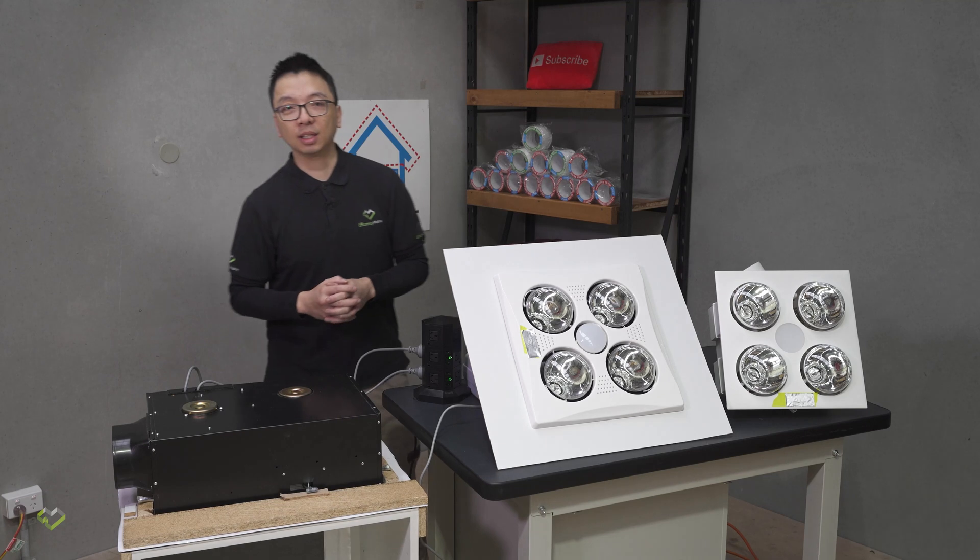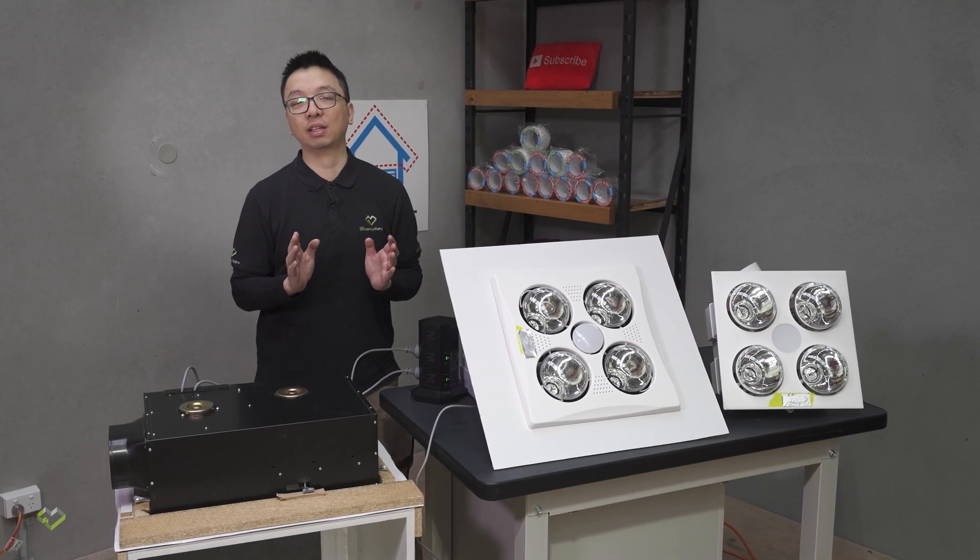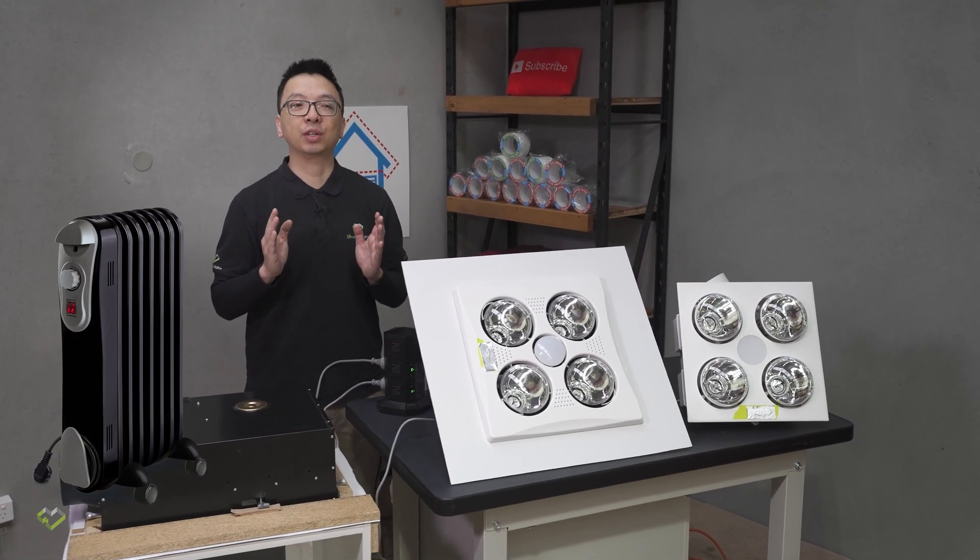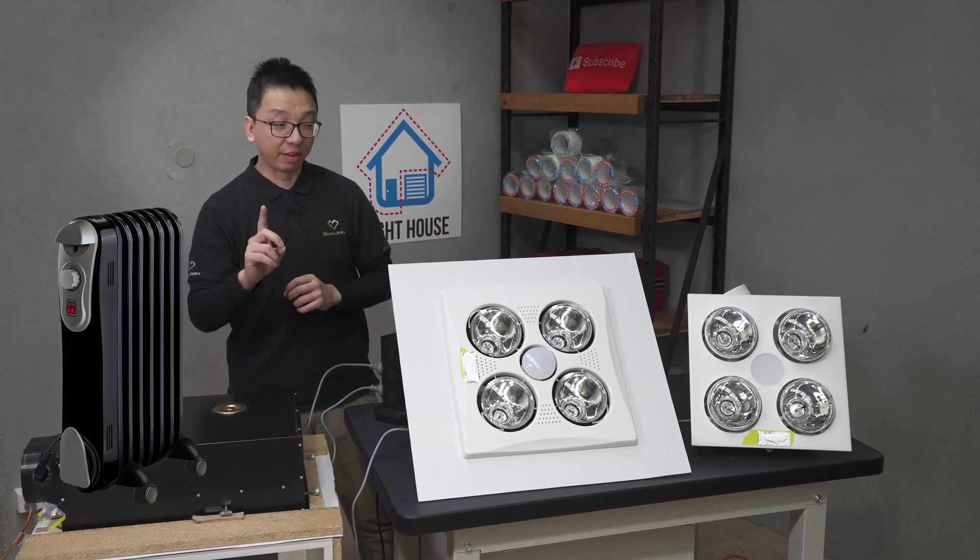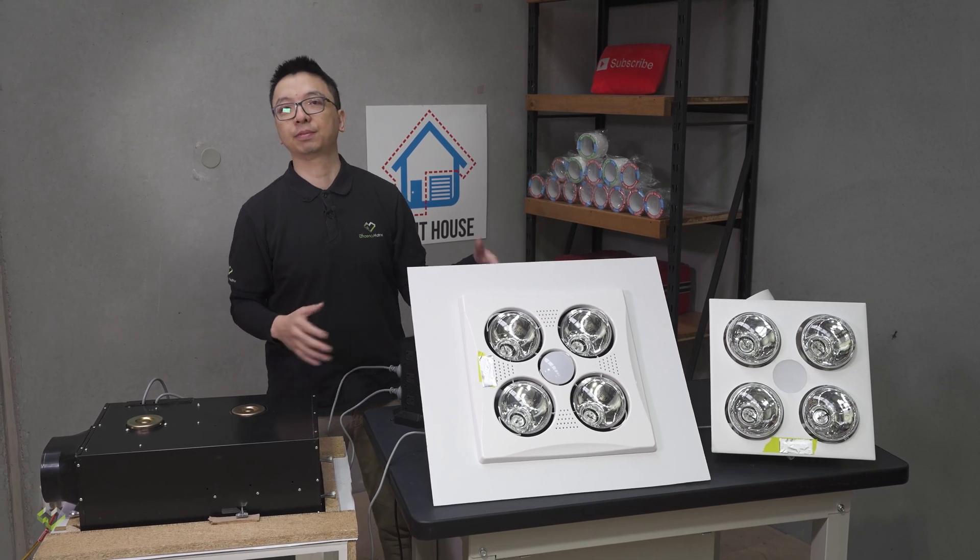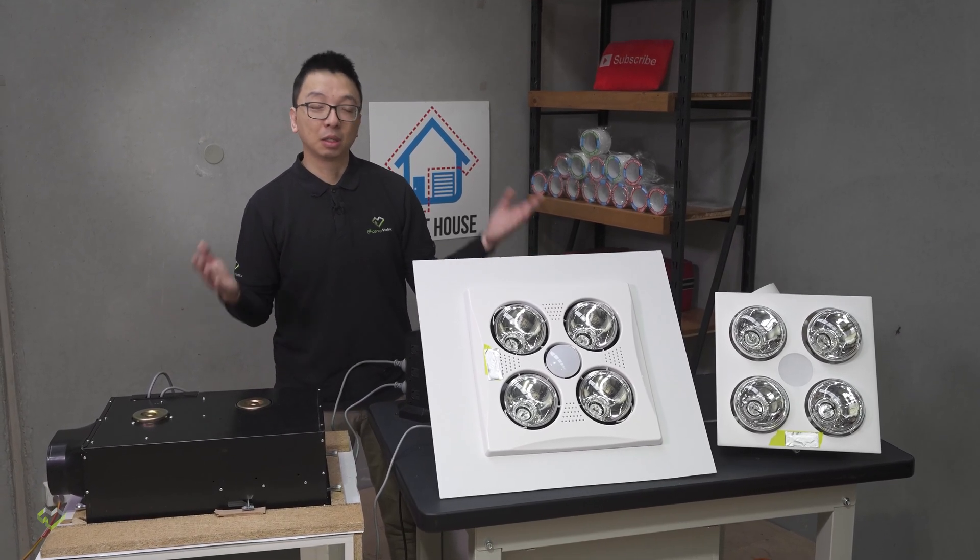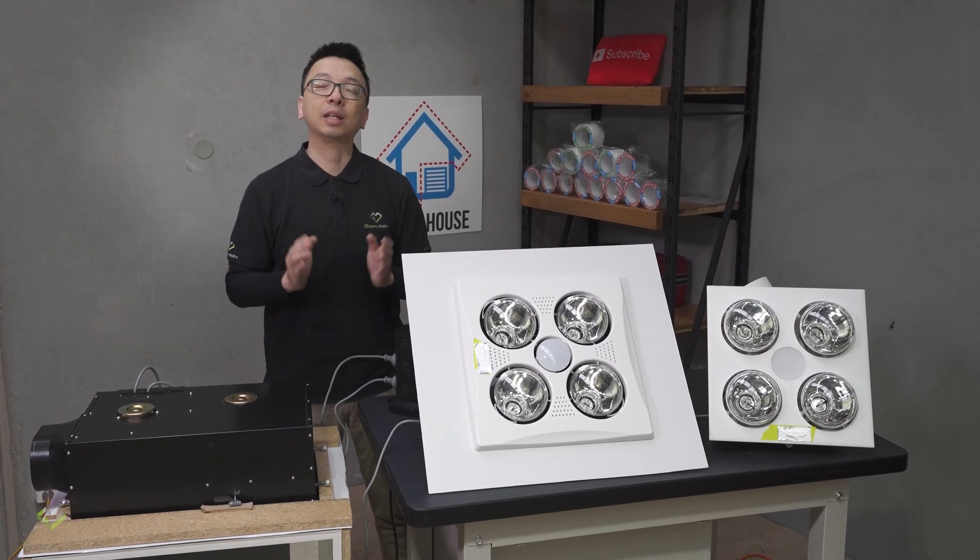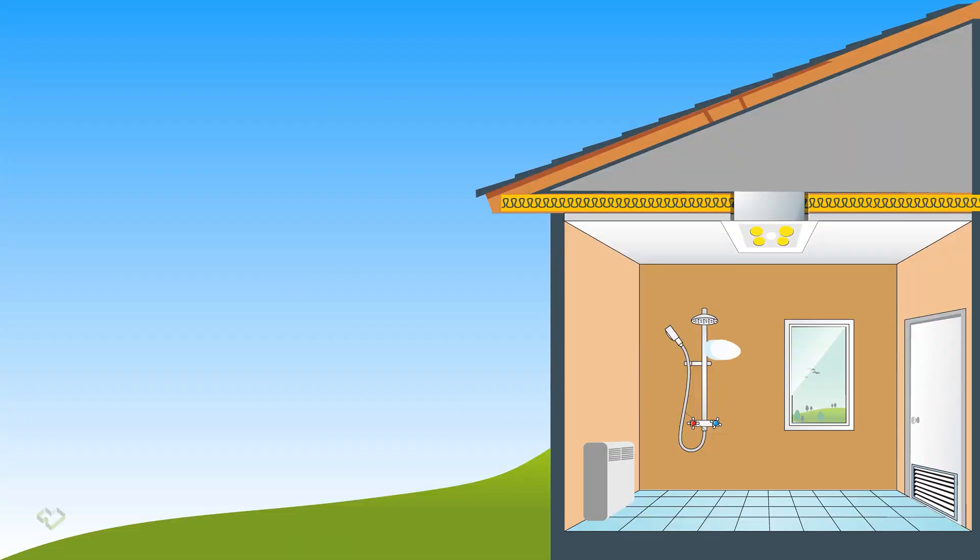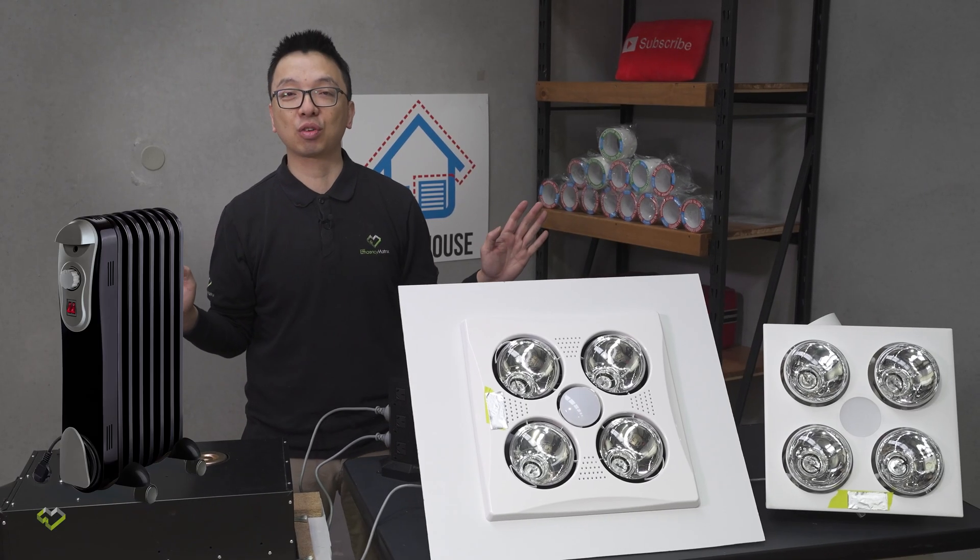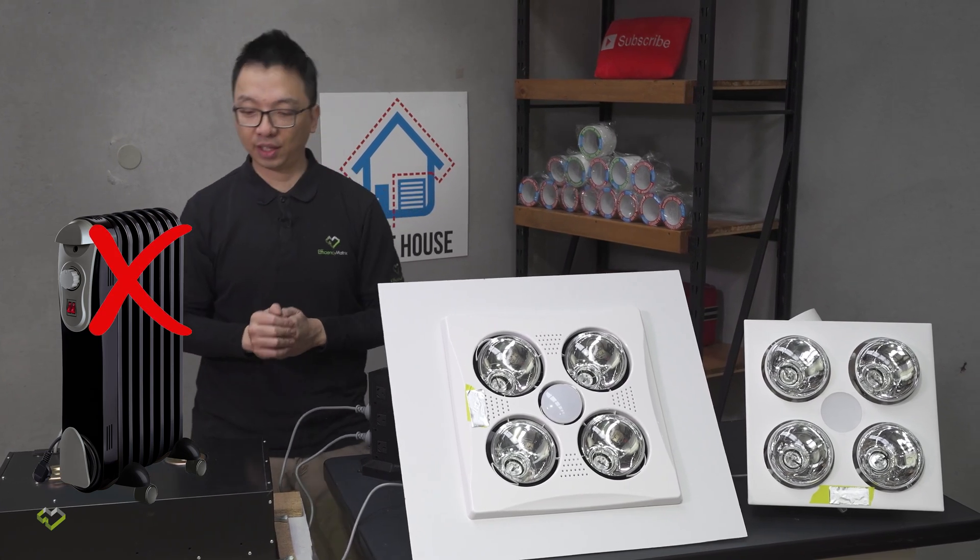Number one, I think we rarely see oil-filled convective heater in bathroom. The number one reason is it relies on natural convection to warm the space up. However in the bathroom whenever we use it, except for if the ladies are putting on makeup, we are almost always running exhaust fan that works perfectly against a natural convective heater. All your warm air rise up to the ceiling and then the exhaust fan just take it out. It will take forever to try to warm up the space. That's why we got a big cross on convective heater.